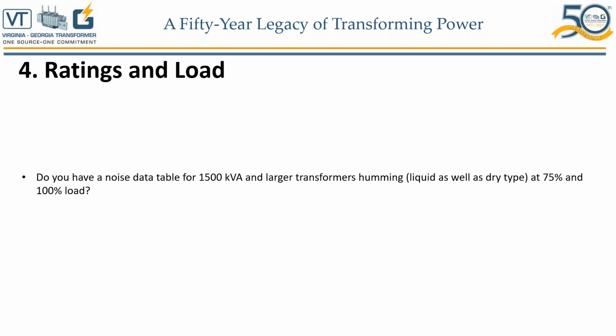However, as the transformer size gets larger and larger, say above 30, 40, 50 MVA, and especially when you get close to 100 and 200 MVA transformers, we know that there is actually a load noise as well. And the load noise is produced by the vibrations of the windings and tank walls when the transformer is loaded. And there is a third element to the sound of transformers. That third element is from the cooling devices, like the fans or the pumps. So the total audible sound of a transformer is now, per the standards, considered to be the sum of all three components: the core, the load, and the auxiliary cooling devices audio.